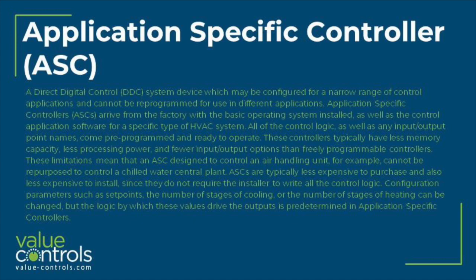Configuration parameters such as set points, the number of stages of cooling, or the number of stages of heating can be changed, but the logic by which these values drive the outputs is predetermined in application-specific controllers.